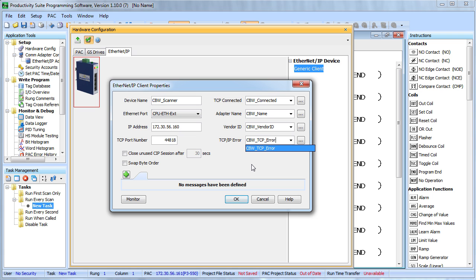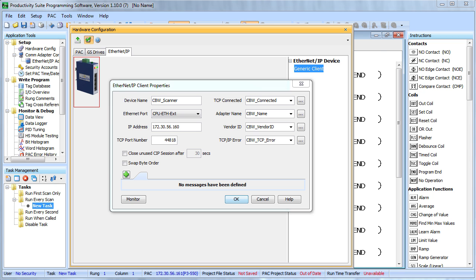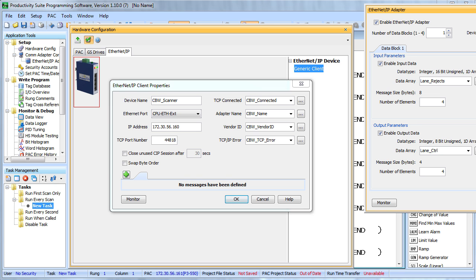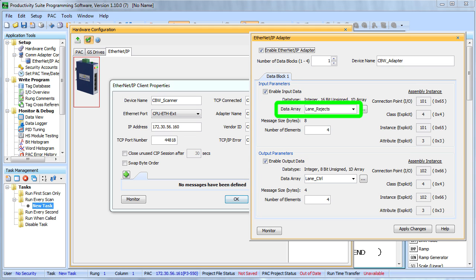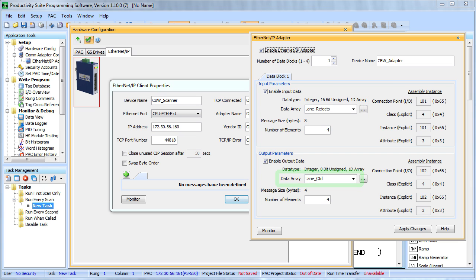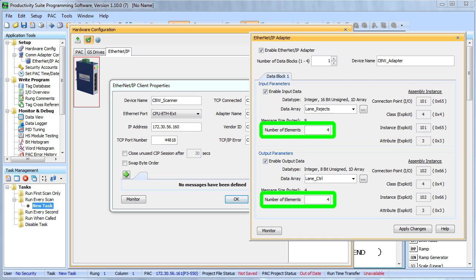For this video, the candy bar wrapper Productivity3000 is very similar to the one we set up in the adapter video. Here's the dialog from that unit. I'm going to keep it on the screen so we can keep an eye on it. But just as a refresher, we had one data block with an input and an output data, we had an array to keep track of the lane rejects and an array that would allow us to control each individual lane. On the previous video, these arrays were like 32 elements large. On this video we set both arrays to be 8 elements, one for each of the 8 lanes of the candy bar wrapping machine. And since only 4 of the lanes are active, instead of sending that whole array back and forth, we limited the amount of data to send back and forth to just 4 lanes to save bandwidth. Again, that was the adapter. Our job in this video is to set up the scanner.